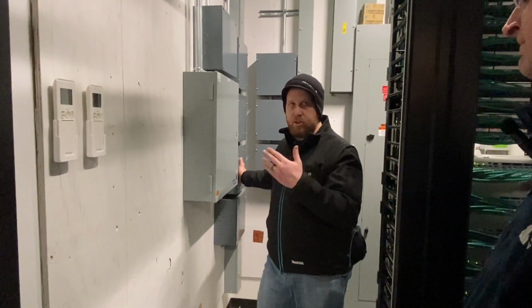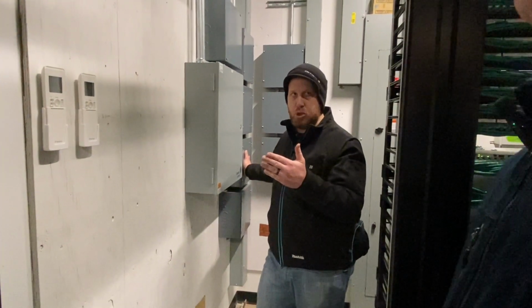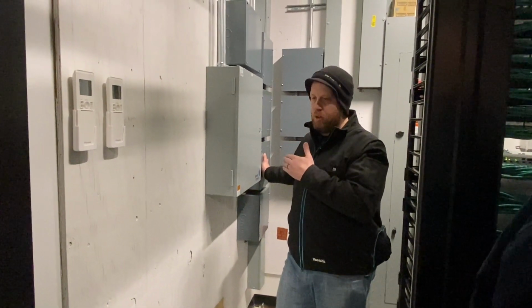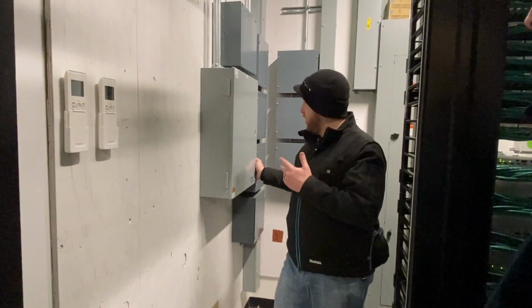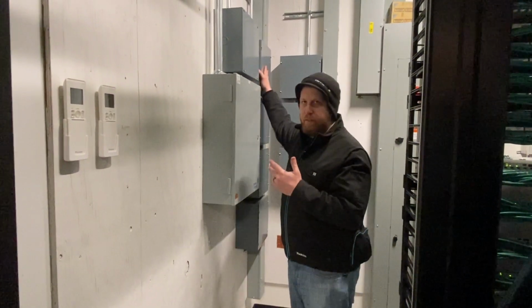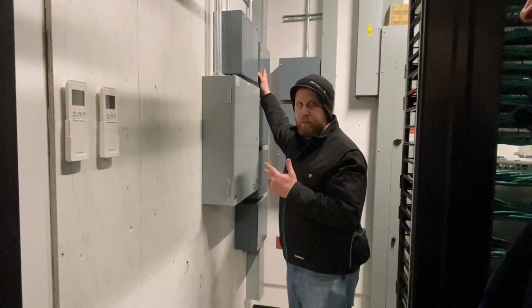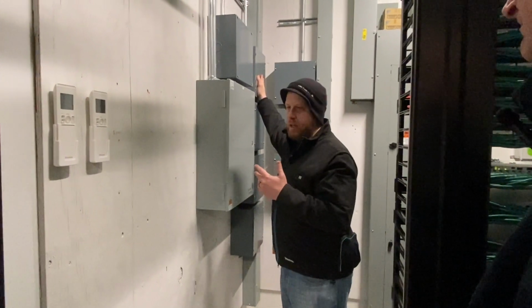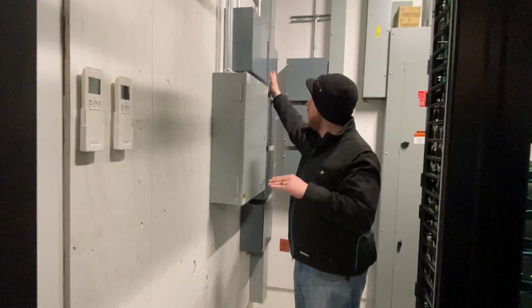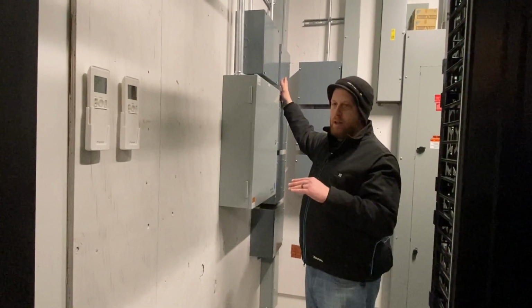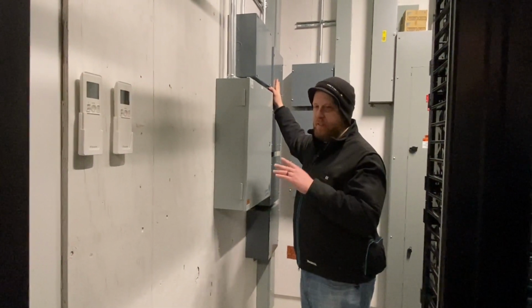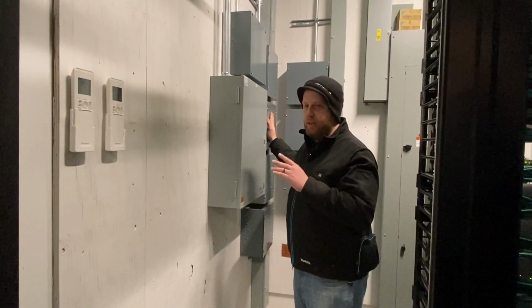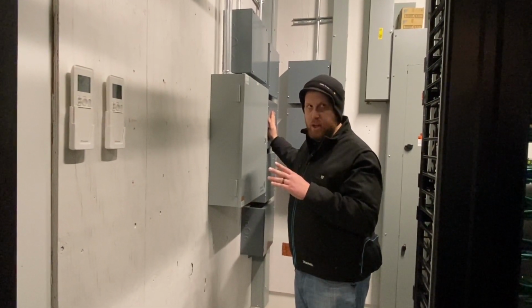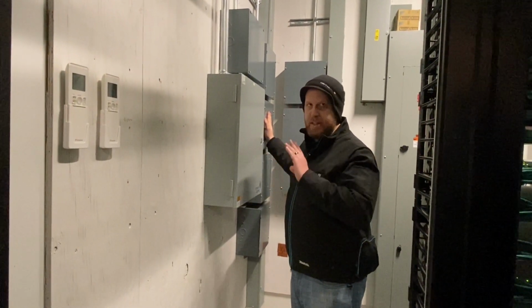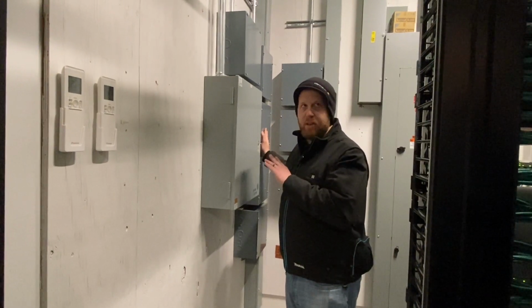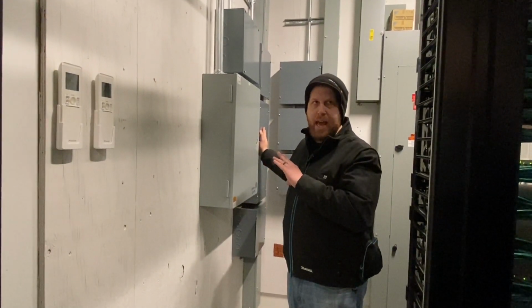The Antec valves are actually fast acting, and they take a lot of juice - meaning a lot of VA, low voltage capacity. So pretty much each one of these has 5 legs of 24 volt power, at 500 VA total, 100 VA per trunk. You can run a lot of the JCI VAVs off of one trunk, but the fume hood controllers, since they're fast acting, have their own dedicated power trunk because they're almost a 90 VA power draw.